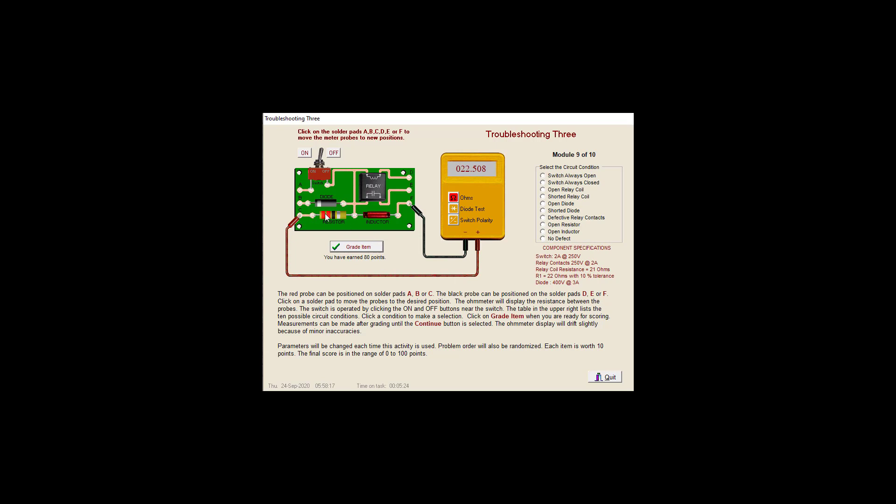22, 220, 22. Good inductor. Let's check our relay. Oh man. So let's go ahead and check and see if we get anything through our switch. Nope. It's our relay that is open. Open relay coil.